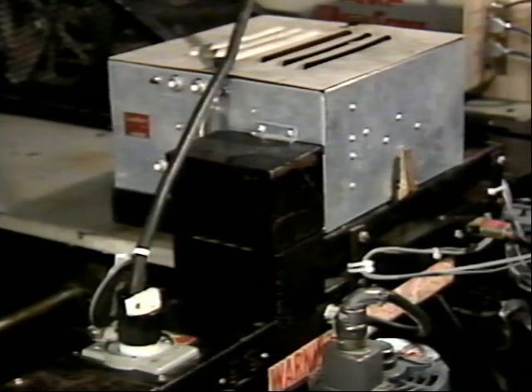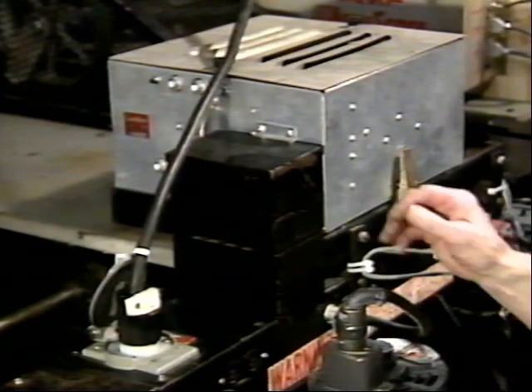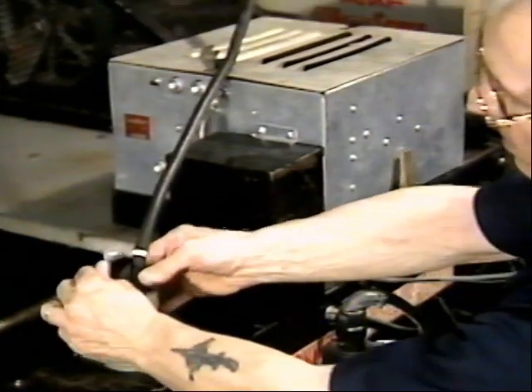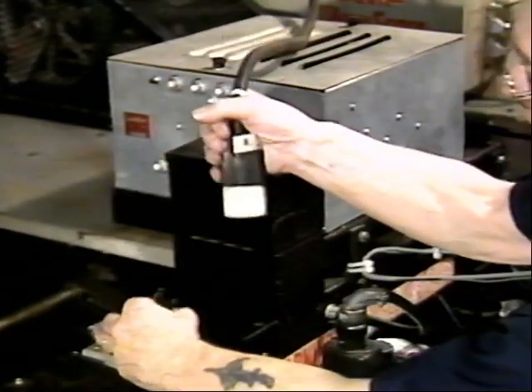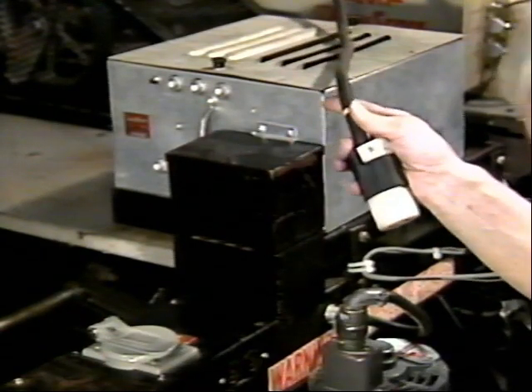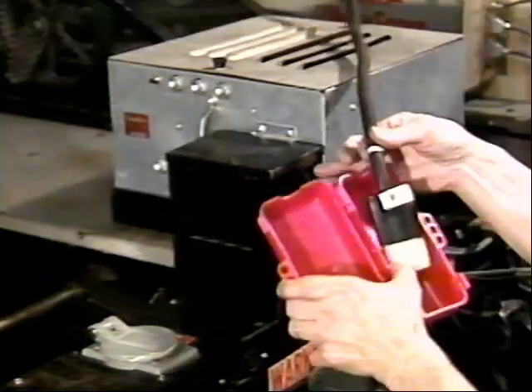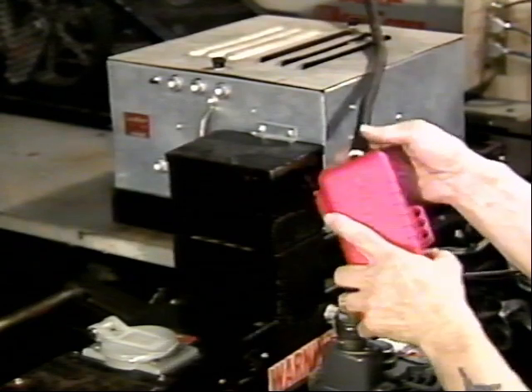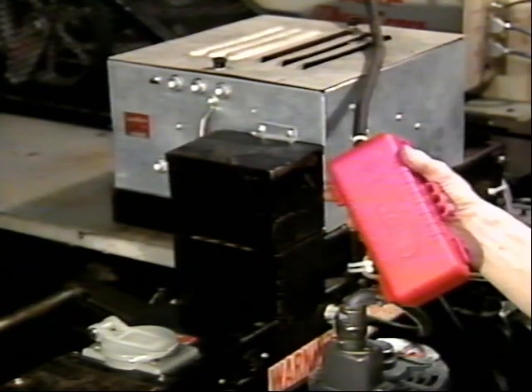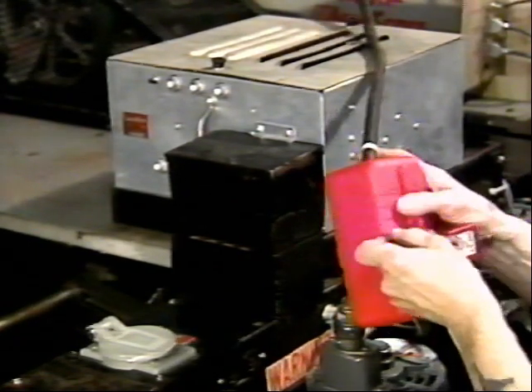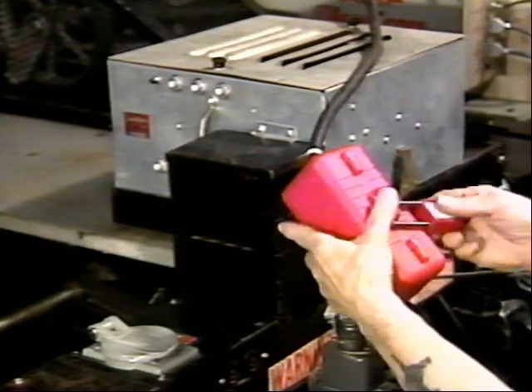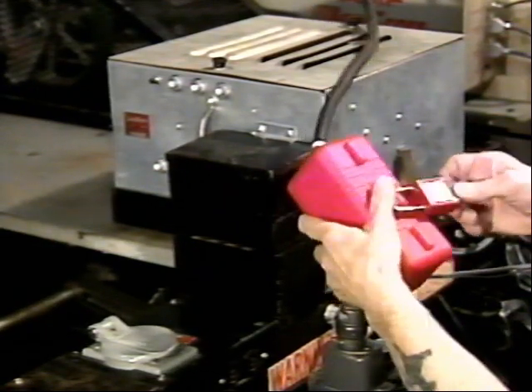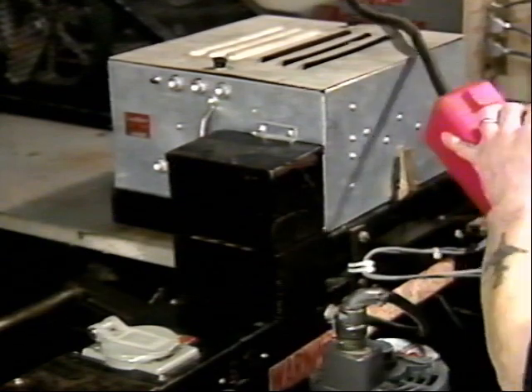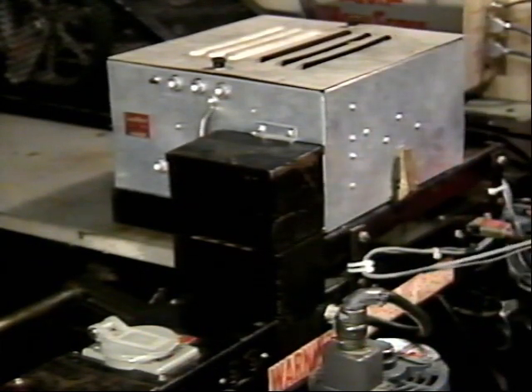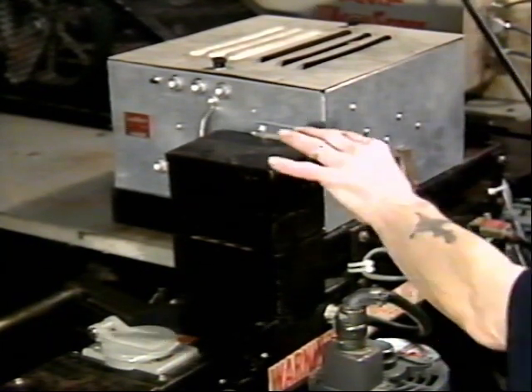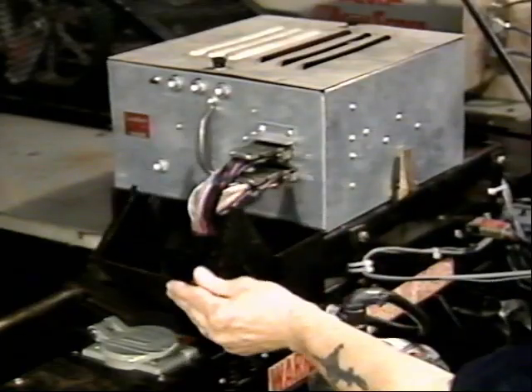However, before the chassis can be removed, the power plug needs to come out. And as always, once the power plug has been removed, for safety, we should put it in a lock box so that no one else can turn this machine back on or attempt to turn it on until we're finished with the maintenance we are performing. So we've locked the box. This machine is safe. The chassis has several control plugs that we find here.